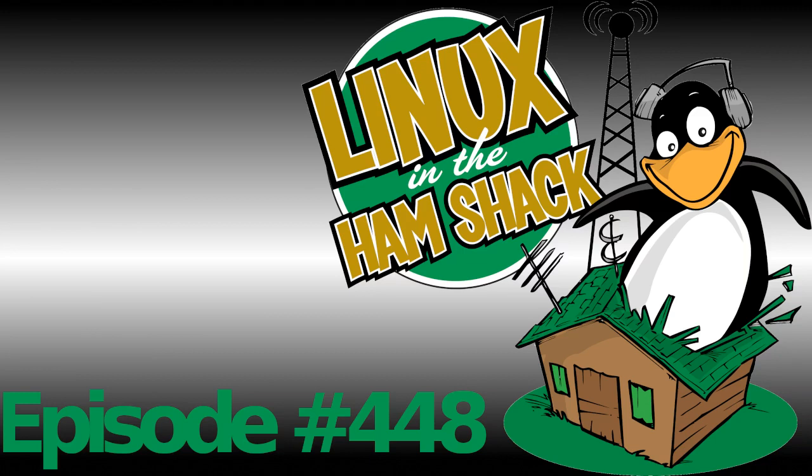Definitely good. They explain what lightning is. They explain how to approach lightning protection in your house. So that's basically the idea with lightning. Low inductance connections, connect everything together, and then connect it to a ground system that is outside your house. Don't run feed lines and ground wires through crawl spaces and attics and all the other stuff. Give Mr. Lightning the path to the ground outside the house. And I'm kind of blowing through this and oversimplifying, but those are the high points for lightning.